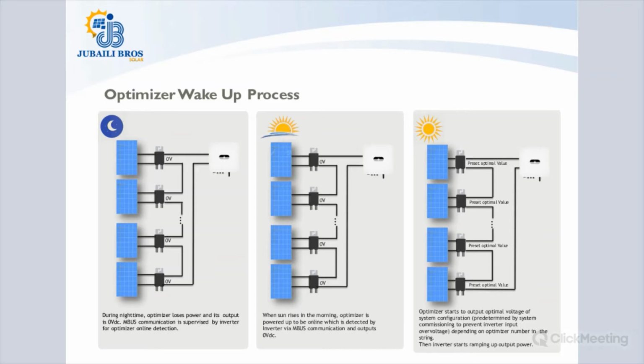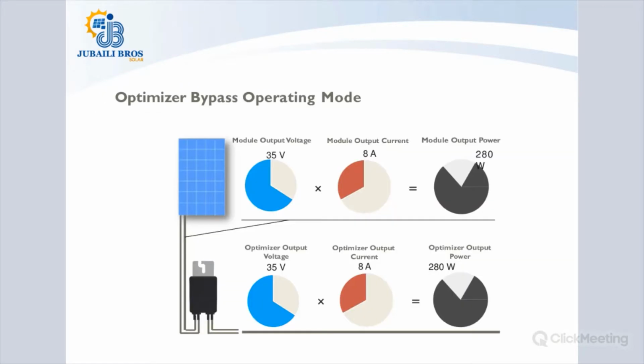It is not anything that you touch. It's not anything that you actually deal with. It's purely automatic. As the PV DC side de-energizes, the PV optimizer also goes down to 0 voltage, and as it energizes in the morning, the voltage is going to ramp up. It's pretty simple. So here we were explaining the bypass process and the back process. For the bypass process, as I explained, you can see that the IV curve of the PV module remains untouched through the PV optimizer. So the wattage is always the same.